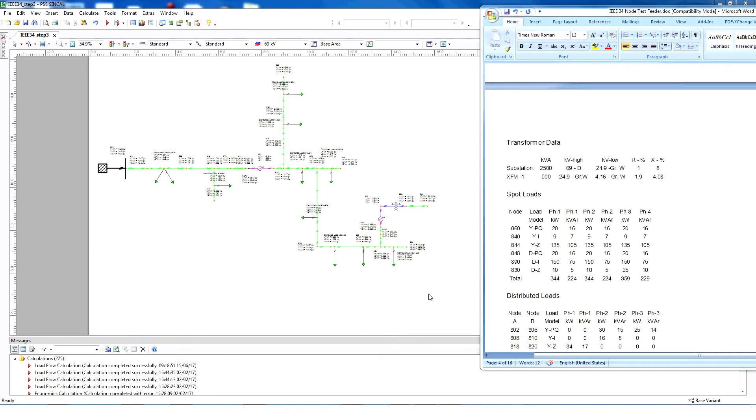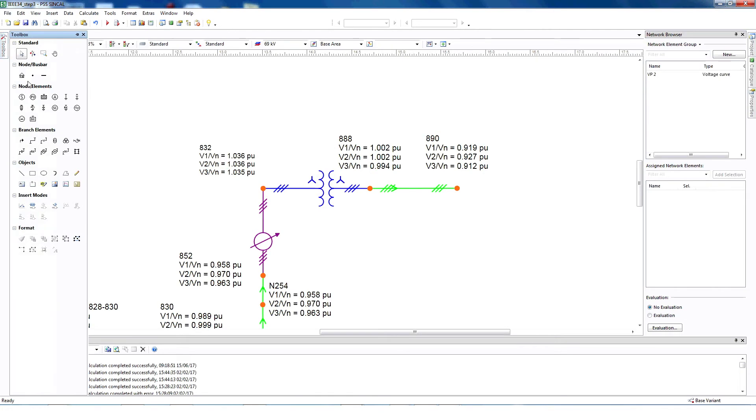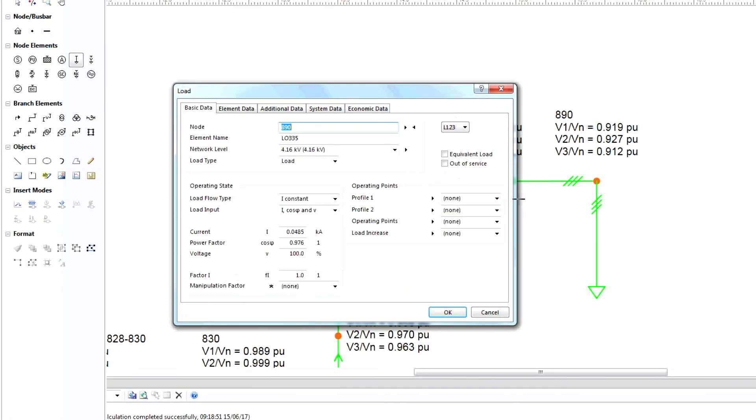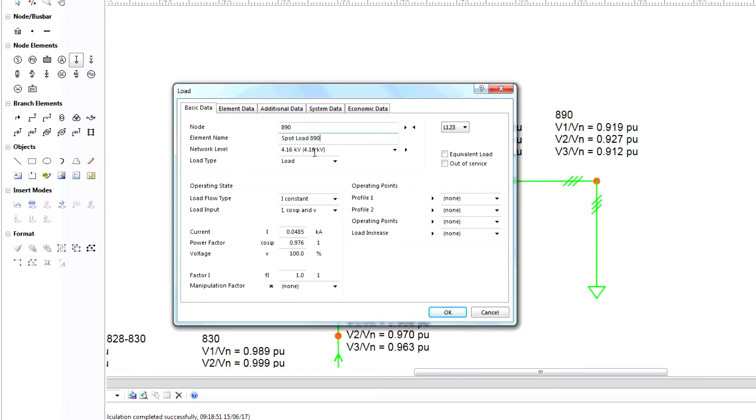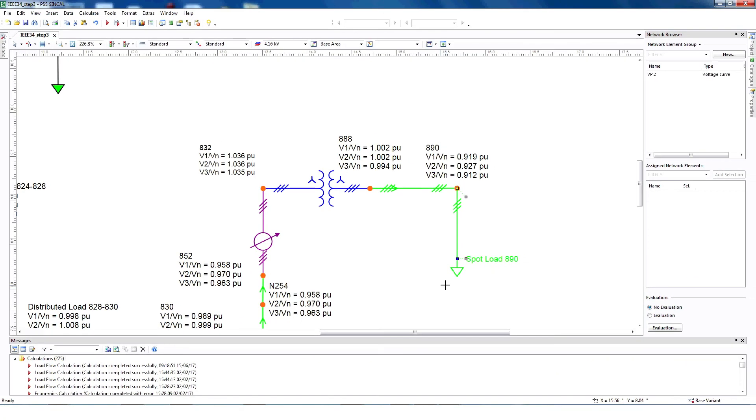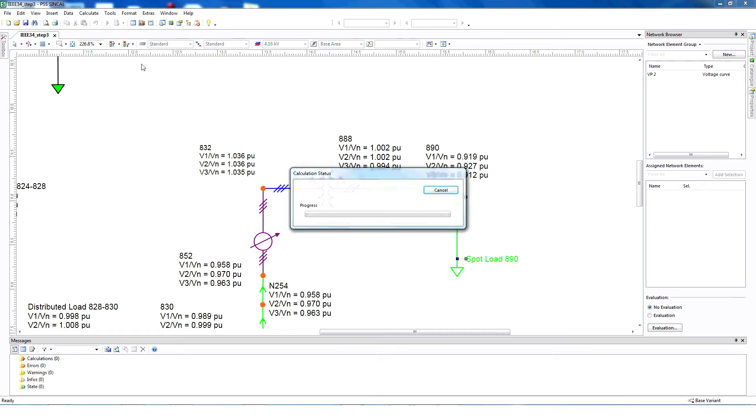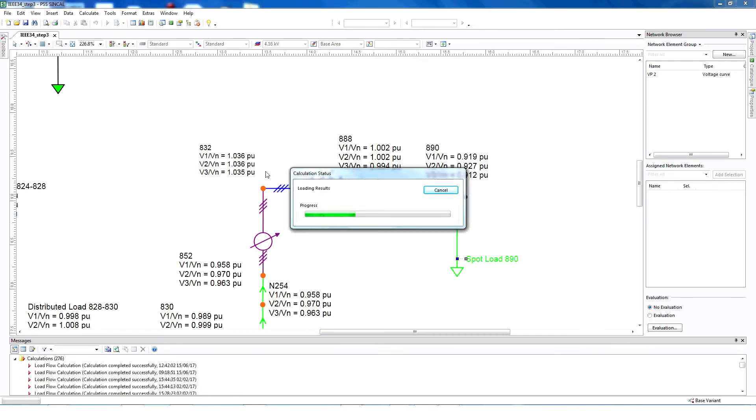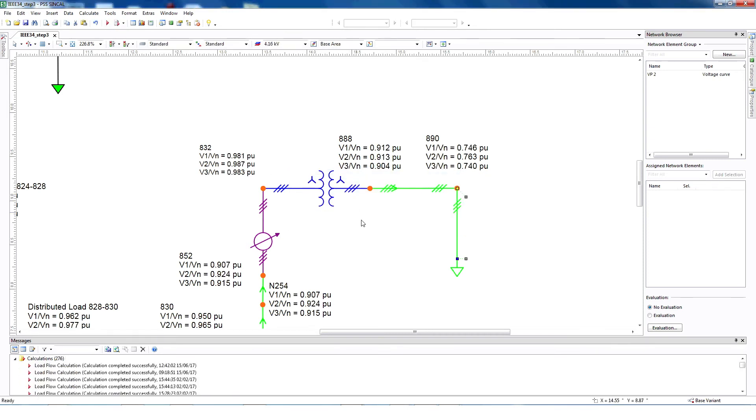Next, let's model a spot load at node 890. To connect a spot load, select load, connect it to 890. It's a three-phase load, so select L123. Name it spot load 890. Add all needed information and then click OK. Please note that if the load is balanced, you can also add the values in total, rather than providing in each phase.